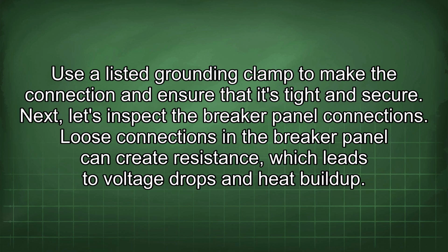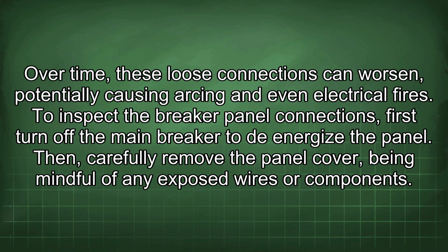Next, let's inspect the breaker panel connections. Loose connections in the breaker panel can create resistance, which leads to voltage drops and heat buildup. Over time, these loose connections can worsen, potentially causing arcing and even electrical fires. To inspect the breaker panel connections, first turn off the main breaker to de-energize the panel. Then carefully remove the panel cover, being mindful of any exposed wires or components.